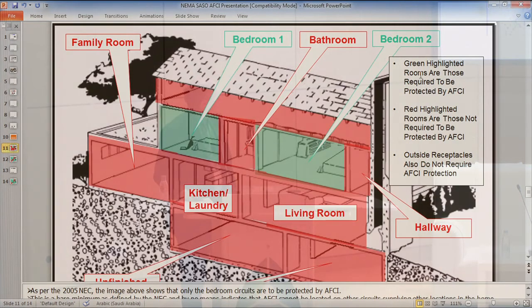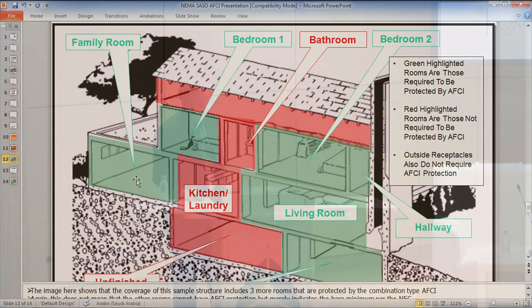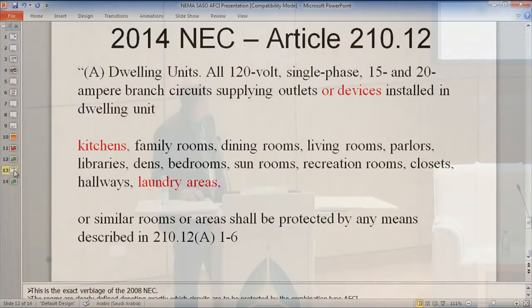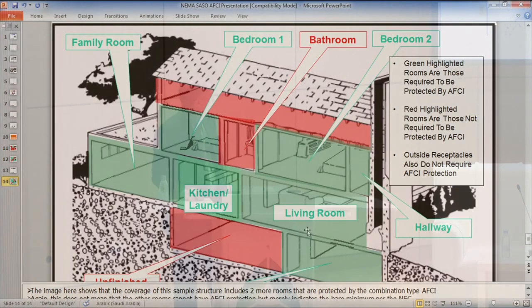If you look at, again, the way we began the process, we had it in the bedrooms initially. This was back in the 2002 timeframe, with the thought that this was the place where most people would be injured if a problem arose. But then as it progressed, we included the other living areas that didn't have ground fault, because the combined device was a bit more difficult. And if we move to 2014, this is the list. Basically, all these rooms and areas are now protected by arc fault and or ground fault and arc fault as a requirement. And pretty much the whole house is required.